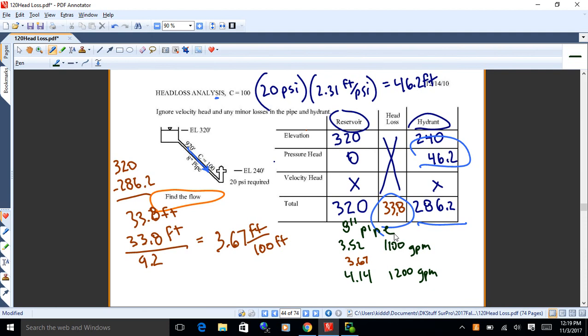All right, so I would say if someone says, hey, if I pull that hydrant down to 20 PSI, what flow am I going to get? I'd say about 1,100 gallons per minute is what I tell them. Okay. And I've not been a firefighter or anything, but I think they have pressure gauges, they try and track what they're doing when they start pulling water. They don't want to pull a vacuum in the system when they're fighting fires. They definitely don't want to do that. Okay. So we okay with that?